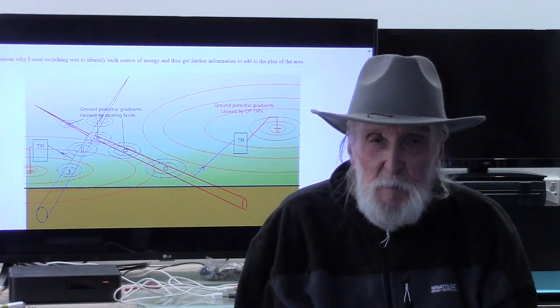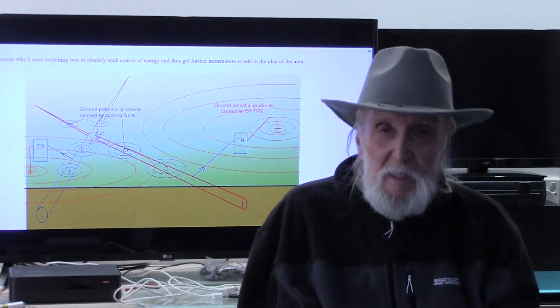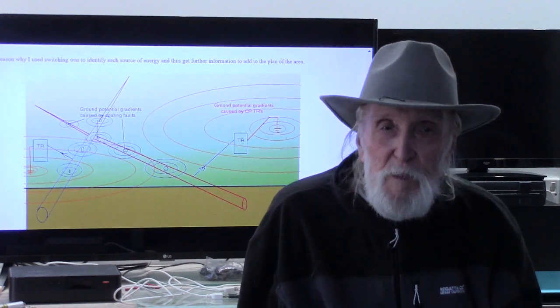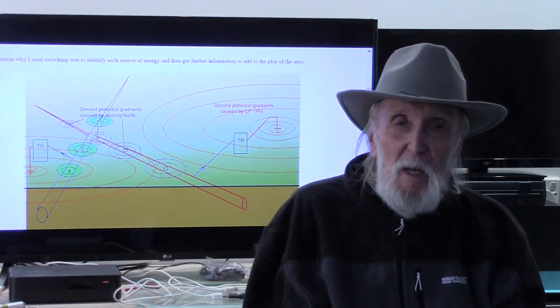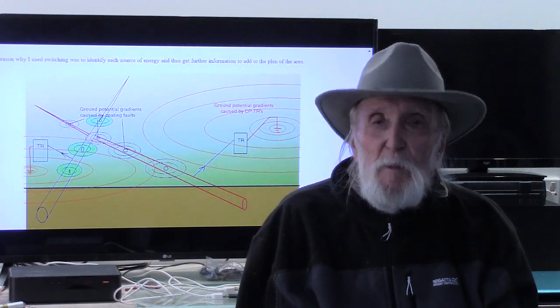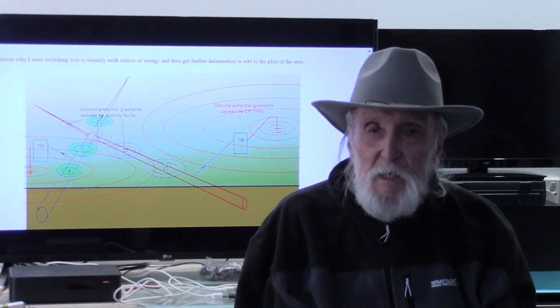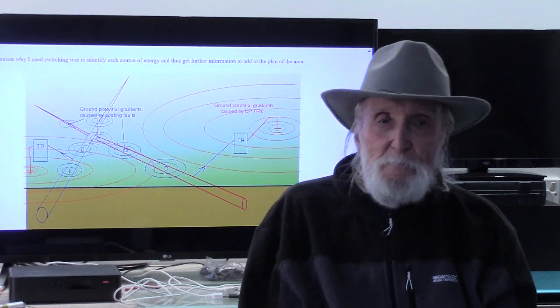This will be detectable on CIPS or DCVG surveys, but the cause may not be apparent until a proper 2 half-cell survey is conducted with that particular ground bed switching.